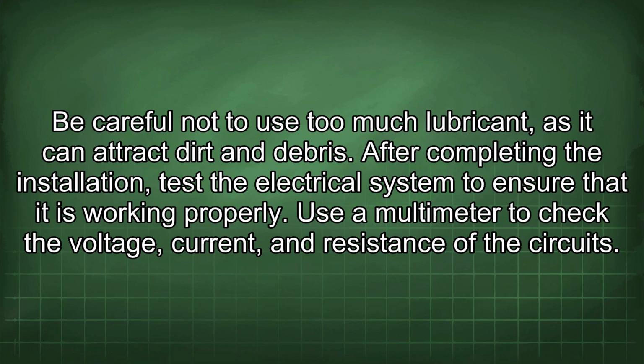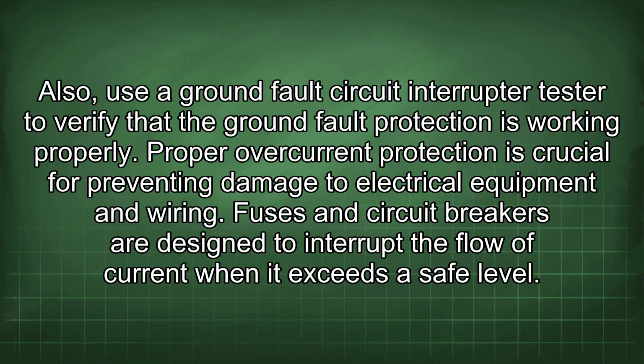After completing the installation, test the electrical system to ensure that it is working properly. Use a multimeter to check the voltage, current, and resistance of the circuits. Also, use a ground fault circuit interrupter tester to verify that the ground fault protection is working properly.